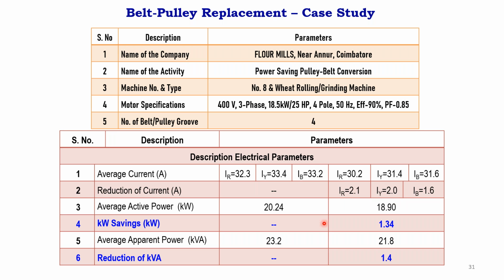We conducted them on the same day when the belt was replaced, and similarly 10 days after that, 1 month after that, and 3 months after that. But almost the value of the power taken by the motor is still the same. Earlier it was 20.24 kilowatt, and now it is 18.9 kilowatt. So we got 1.34 kilowatt as the difference in power from the old existing belt to the new belt. Not only the kilowatt, there is also a small reduction in the kVA.